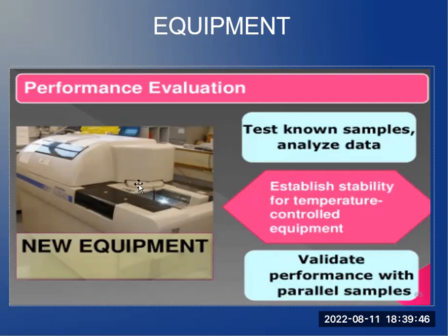Then the equipment should be temperature controlled, since the equipment will generate heat. So the equipment should be placed near the air conditioning unit. That's why when you come into the laboratory, you will feel cold, since the normal temperature in the lab is 20 to 24 degrees Celsius, since the lab contains different kinds of equipment, especially as your lab is very small, not wide.